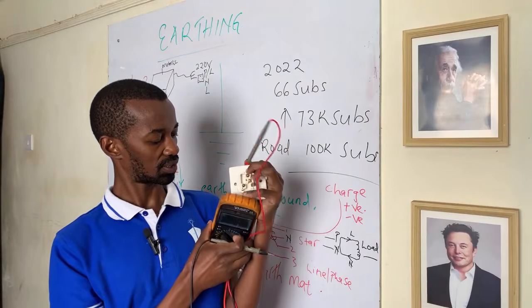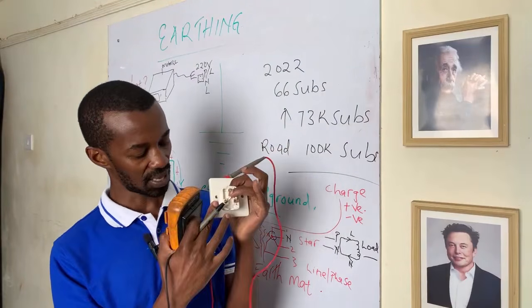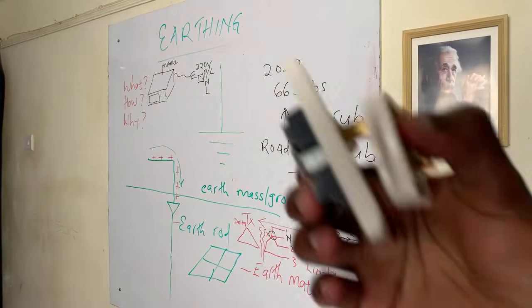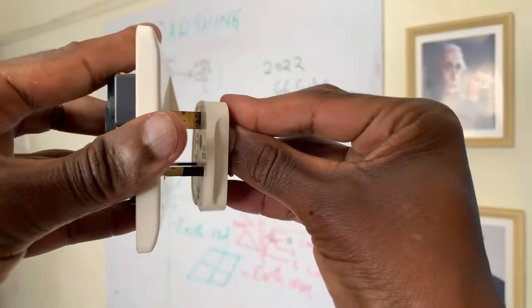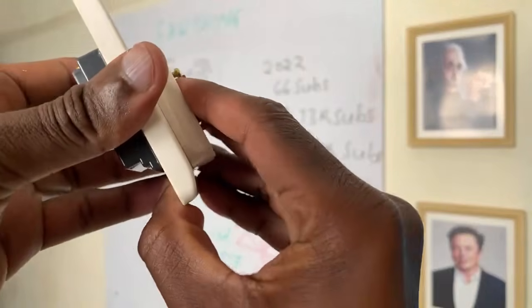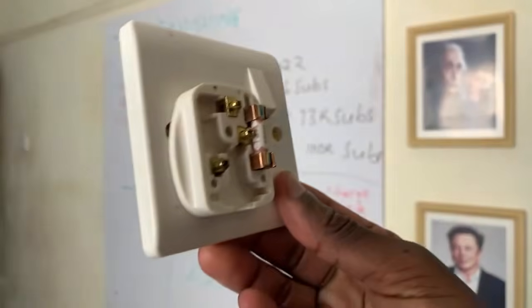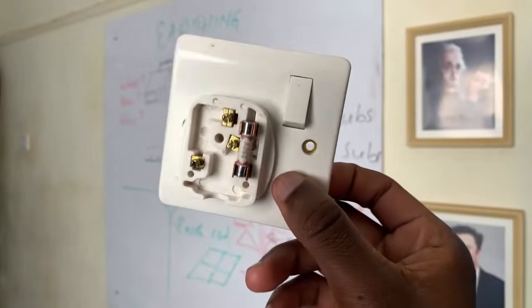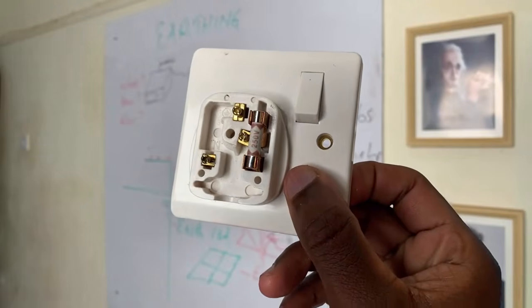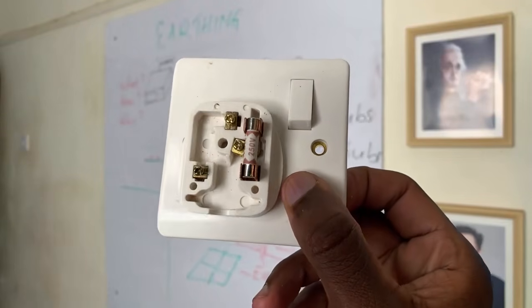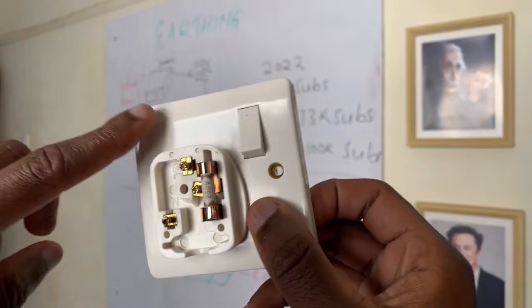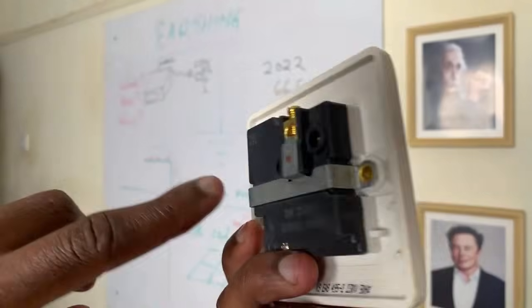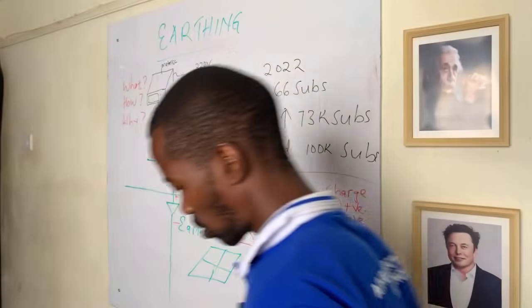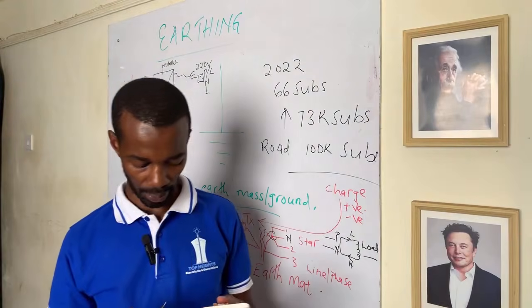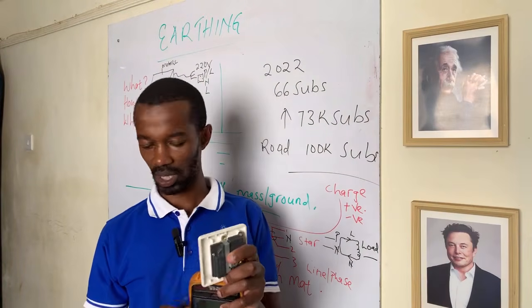Yes, it is in contact, and note that the other two pins are not yet fully inserted in the socket. The moment we insert it like this, even when the switch is off, before we switch it on, we record the continuity between this earthing point and the earthing in the socket. Should we get a result of continuity, will it beep? That's what we are looking for.